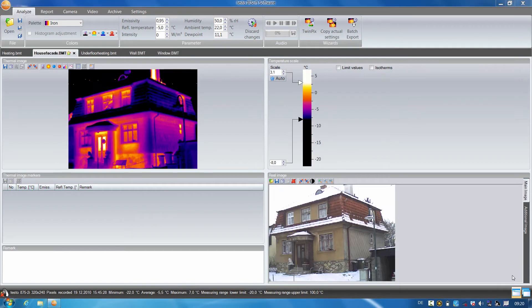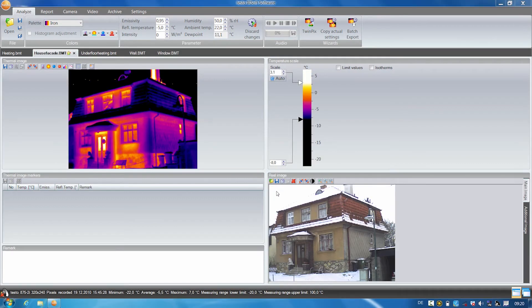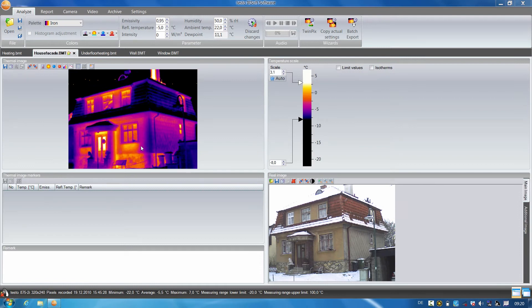First of all, I'll show you how to use the profile line function. In this thermal image, there are cold bridges visible on the front of the building, here under the windows.